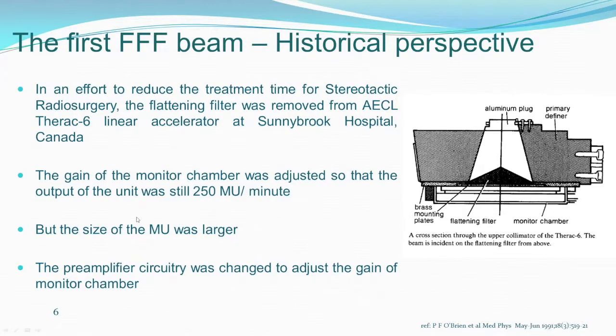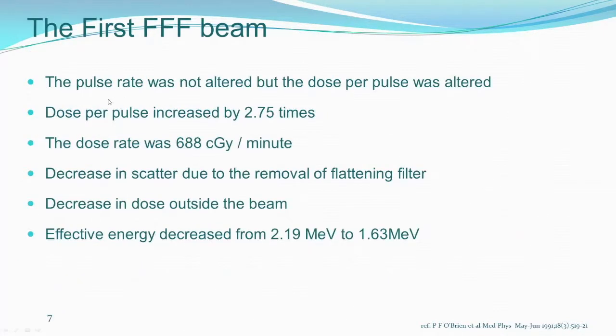Right now, when you do your calibration, you keep 1 cGy per MU, but the number of MUs per minute is higher. For example, 10 MV is 2400 and 6 MV is 1400 or so. But they kept the MU per minute constant and increased the size of the MU, that is the dose per MU. The pre-amplifier circuitry was changed to adjust the gain on the monitor chamber, which is now looking at a higher dose per MU. As I said, the pulse rate was not altered, but the dose per pulse was, increasing by about 2.75 times. Now they were getting 688 cGy per minute instead of 250 cGy.